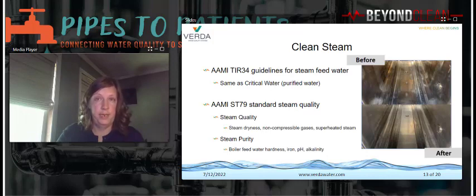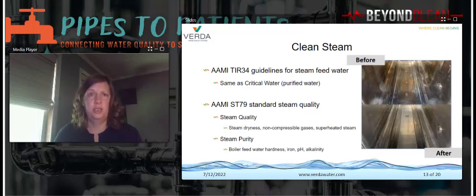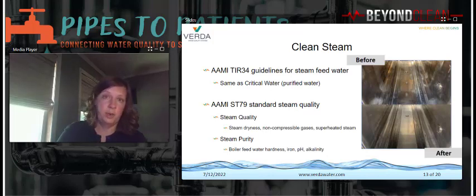For instance, many healthcare facilities soften their municipal water supply, but they're unknowingly feeding treated water that's still too hard for producing high-quality steam for sterile processing. With water softened to between 4 to 16 milligrams per liter, which is considered soft water, the hardness will still accumulate chalky spotting and deposit formations over time. This results in more frequent sterilizer chamber cleanings and shorter lifespans on medical instruments.